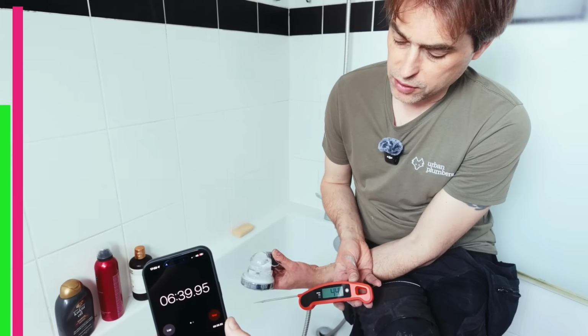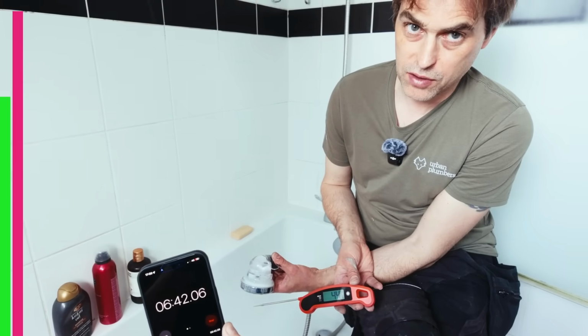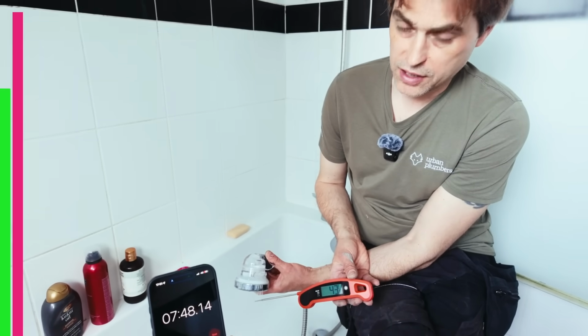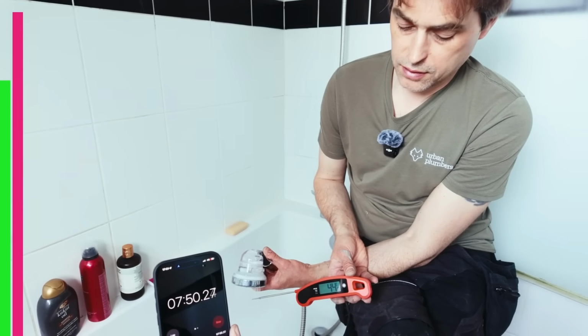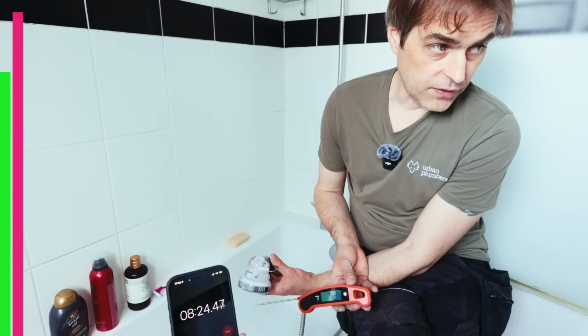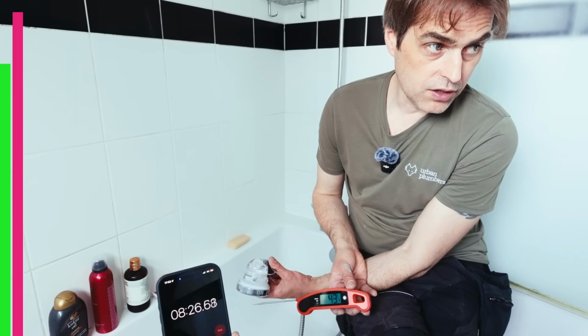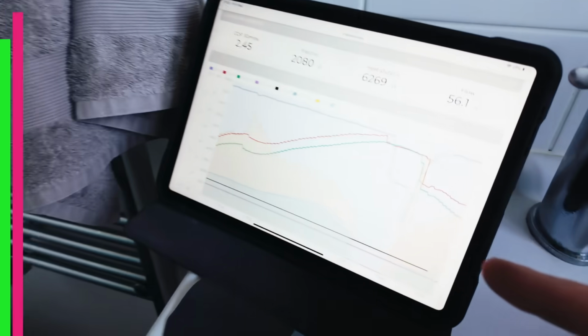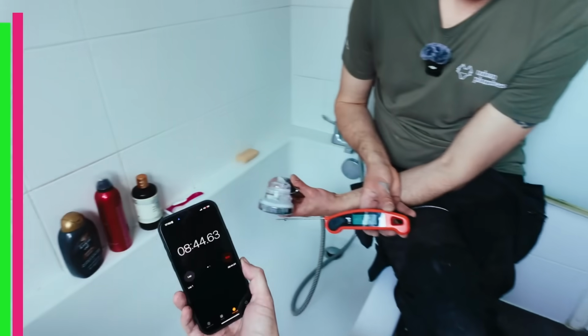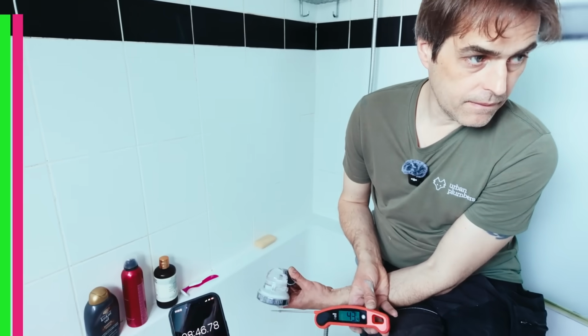Yeah, because that would need what? 7-8 kilowatts to run at this flow point? It is better than a combi boiler. It doesn't drop the temperature. Yeah, and it's smaller. And the flow temperature dropped 2 degrees now. So it's dropping, but it's dropping very slowly. That's what we want, yeah. Very slowly. Even though it's dropping, it's ramping up in power output at the same time, so it's doing its best to stop its cooling rather than adding heat.